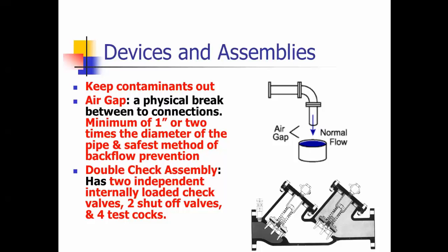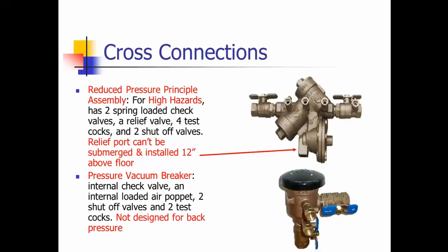A double check assembly has 2 independent internally loaded check valves, 2 shutoff valves, and 4 test cocks. An RP, reduced pressure principle assembly, is for high hazards. It has 2 spring-loaded check valves and a relief valve, which is located right here. There's 4 test cocks and 2 shutoff valves. If you see this dump port, that's an RP.